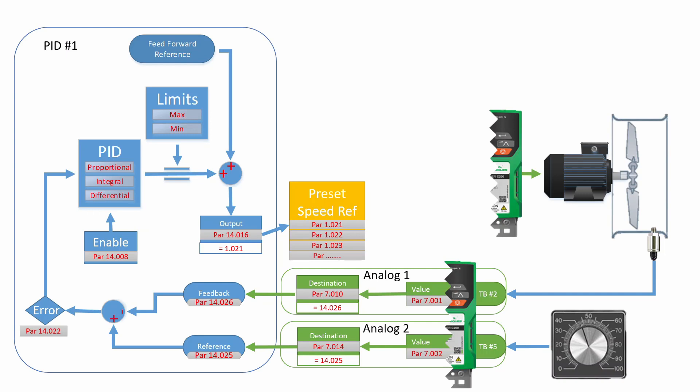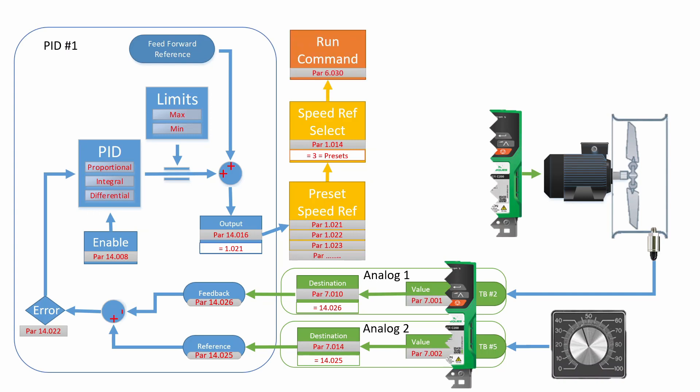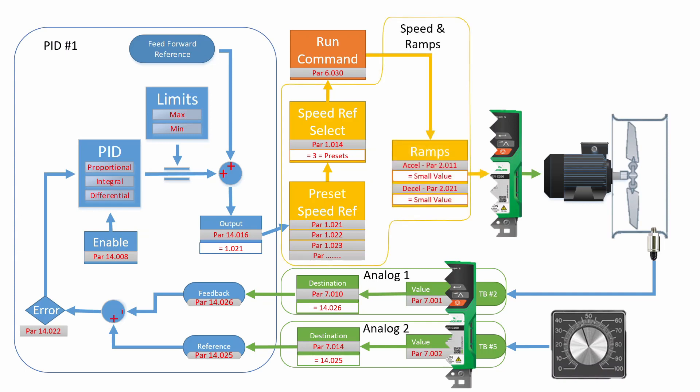Now this output could be mapped to many locations in the drive. One common location is the preset speed references. I'm going to use preset speed reference number 1. Parameter 1.21 is the location for this preset speed reference. In the drive, there are many preset speed references. You need to make sure that you have number 1 selected. The next thing you need to do is set parameter 1.014 to presets.